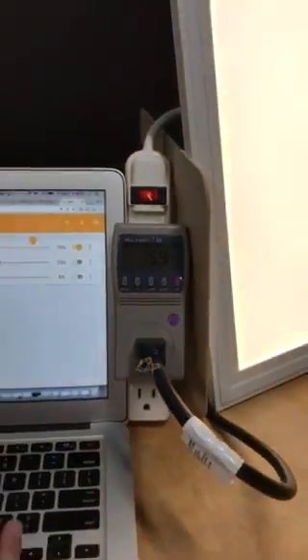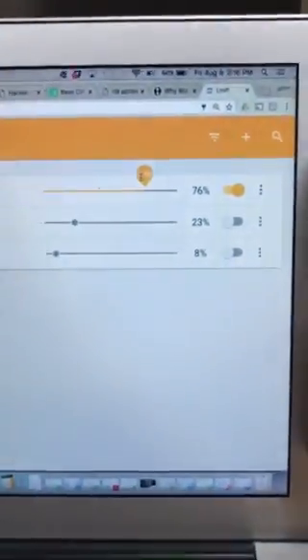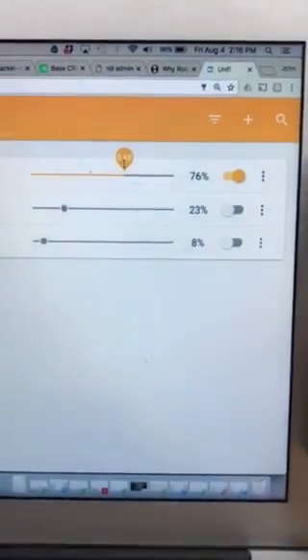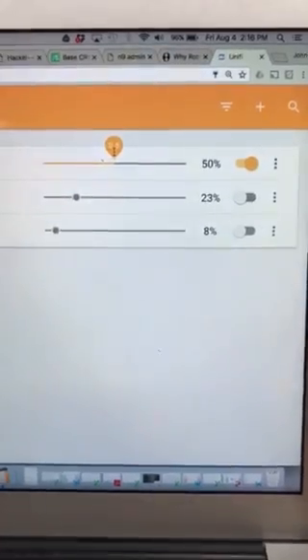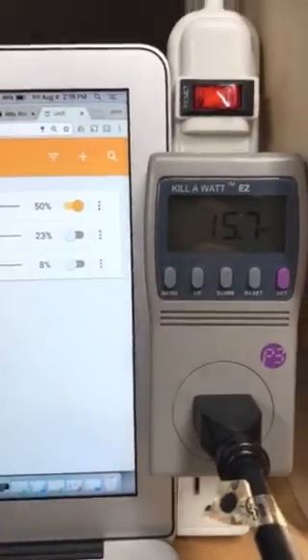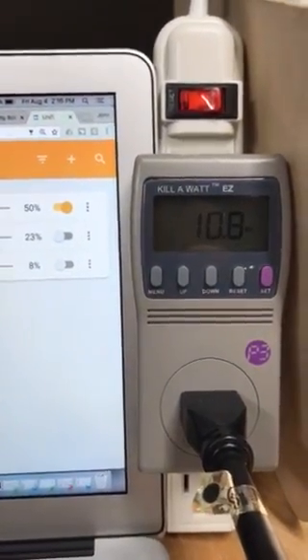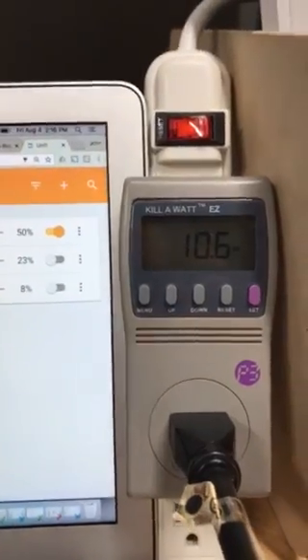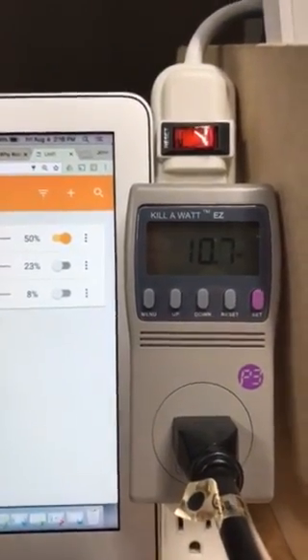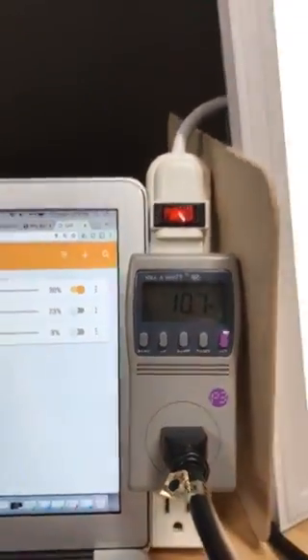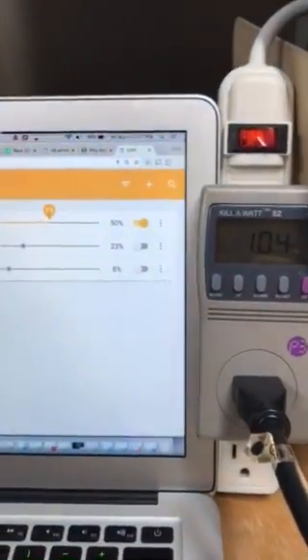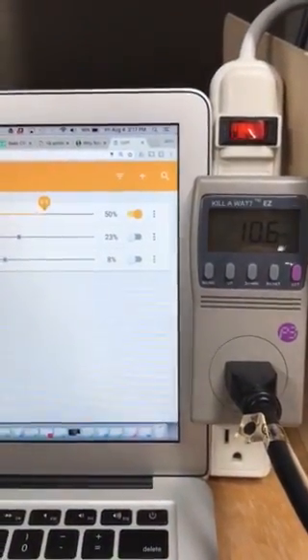We'll just step down to 50 percent — a very achievable blend with daylighting for offices where you have a lot of natural light coming in the window. At 50 percent, the wattmeter is showing system watts at about 10.6 to 10.7 watts, very stable. I'll give you a mapping of the full dim curve in 5 percent increments, but it's very common to be able to dim your lights 50 percent using natural daylight in areas like office towers.